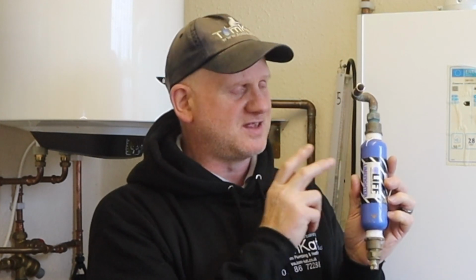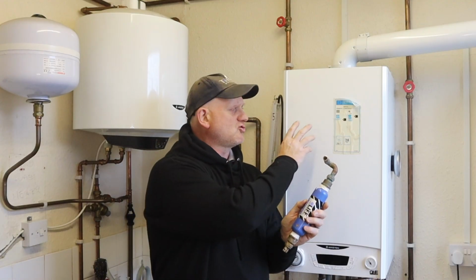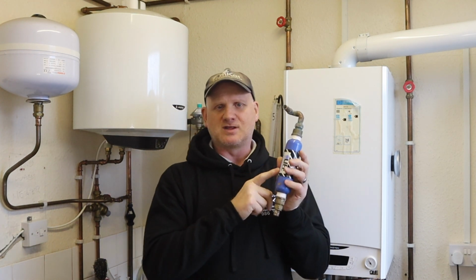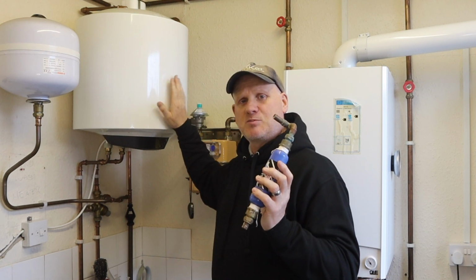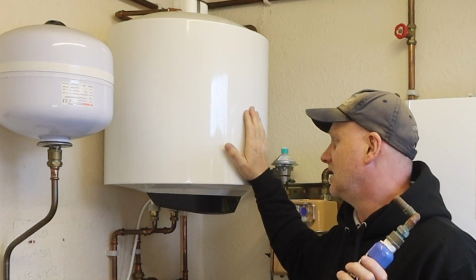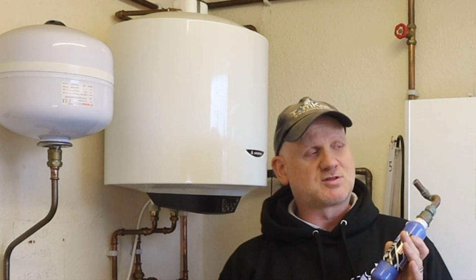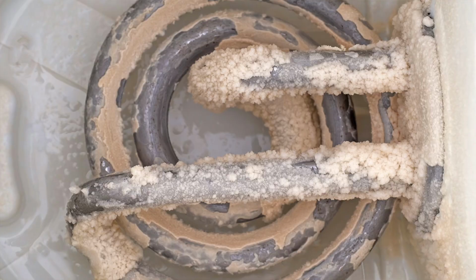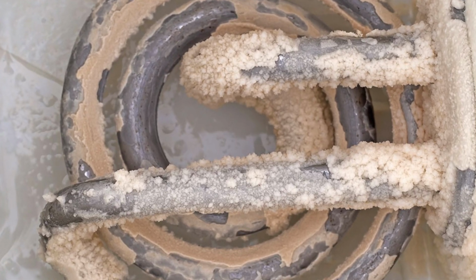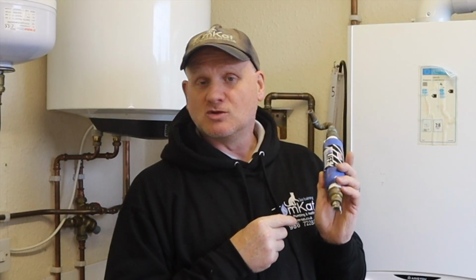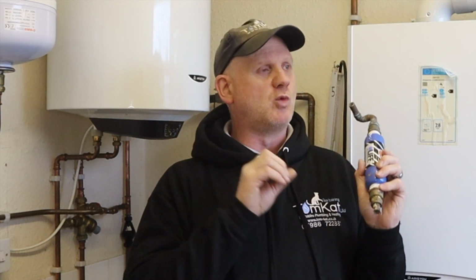Little things like this are about. Again, this is a magnet, but what this magnet does is, instead of catching magnetite, it somehow chemically turns the limescale into something that doesn't stick and it just comes out of your tap. But we don't really fit these. We've got to consider these if you live in a hard water area. Now, they don't just have to protect combi boilers by using these. You can put this in your mains cold, and you can actually protect things like this little unvented cylinder here of hot water from limescale. I'm guessing if you put this on your mains coming into your house, will it protect your kettle from limescale also? I know, maybe it does, maybe it doesn't. But these little things need to be considered to also protect the boiler from the water quality of the town's mains coming into it.